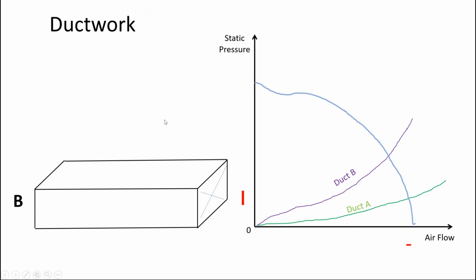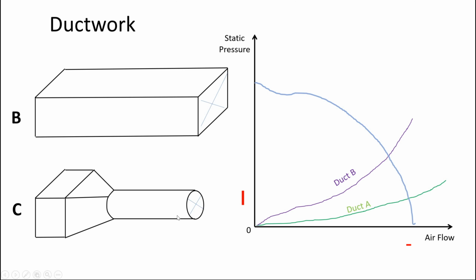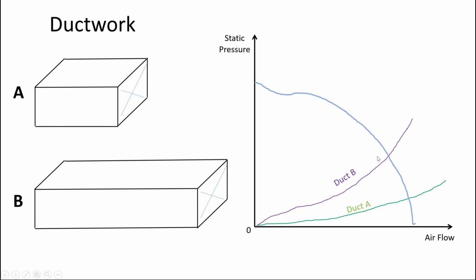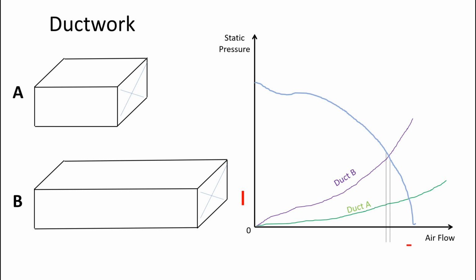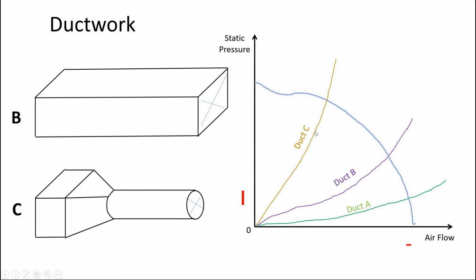Before we go to ductwork B, let's check another example with ductwork C. This ductwork has a high static pressure. The graph for this ductwork would look like this. In this example, it goes on top of our fan curve. In this case, small changes in static pressure will cause high changes in airflow. Again, our fan will not run stable. Now, let's go back to our case B. With ductwork B and the current settings for the fan, small changes in static pressure will not cause significant changes in airflow, and vice versa. This intersection of the fan curve and system chart is also called the operation point. In our example, the operation points of ductwork A and ductwork C are located in the area of instability, while ductwork B is in a safe operation zone.